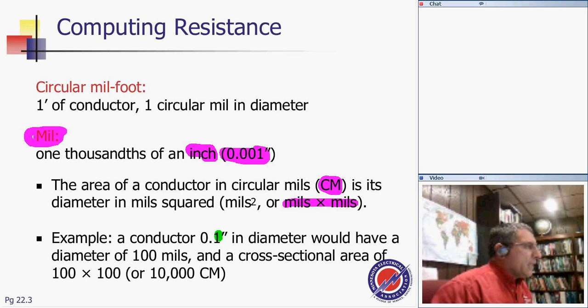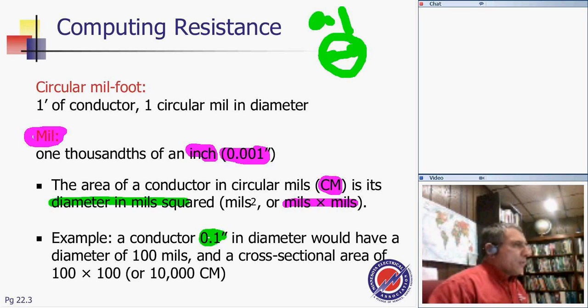The mil is actually the diameter of the conductor. Suppose I have a conductor. Here's my conductor. I'm going to exaggerate here. And the diameter of this conductor right in here is actually 0.1 inch. So 0.1 inch, my friend. If you convert the 0.1 inch into mils, you basically multiply by 1,000. That will give you 100 mils, right? Because 100 divided by 1,000 gives you 0.1.